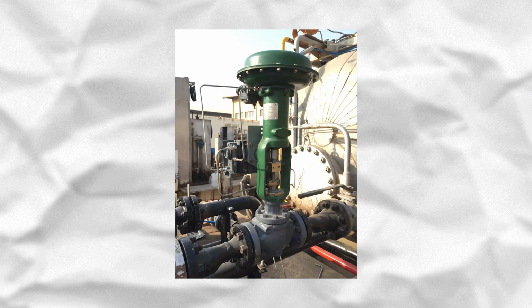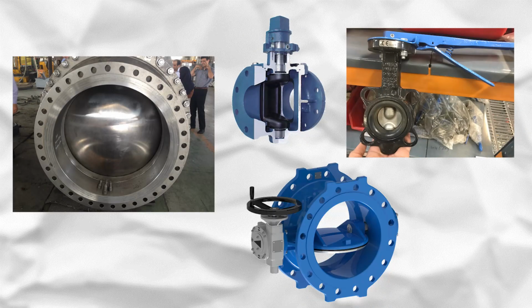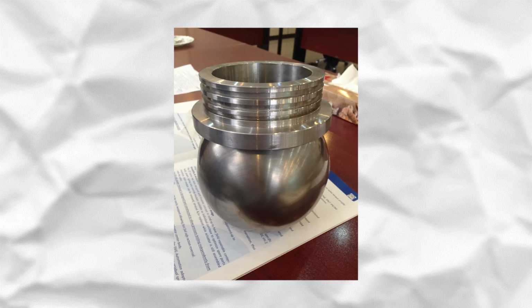By means of creating a differential pressure, the valve can control the amount of flow passing through a pipe. The best valve for this application is a globe valve. However, it has some constraints such as low capacity and limitation in size. Besides, they are too expensive. In some applications, ball valves, plug valves, butterfly valves, and even eccentric discs might replace a globe valve. Valve body material is usually carbon steel and its standard is ASTM A216 WCB, which is cast carbon steel. The internal parts exposed to the fluid are called valve trim, and it is often made of stainless steel 316. Globe valve is also known as a sliding valve due to moving vertically.